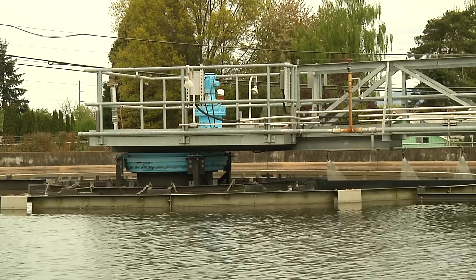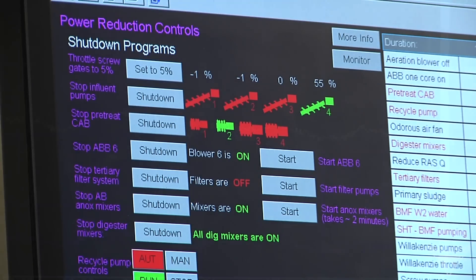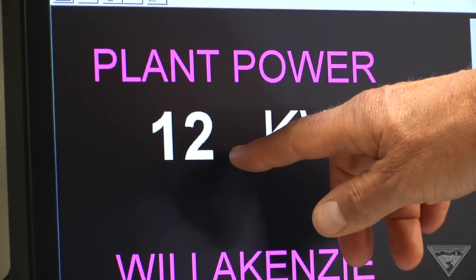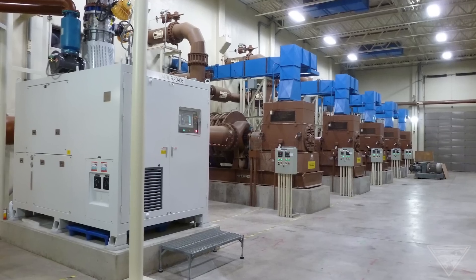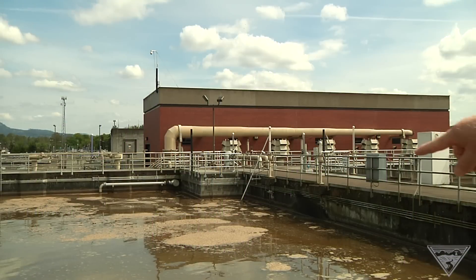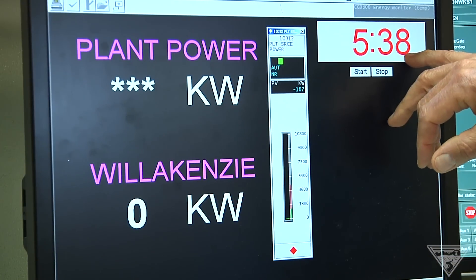As part of the pilot project, the facility was put through a series of tests to find out if it could drop its energy load, keep it at a minimum level for an hour or longer, and do so within 10 minutes. The first thing we would do is hit the blower, because that's the big ticket item. The blower has two cores, and so for long duration periods, we would turn the blower off and deactivate the second core so only one core could start — getting us through four-hour events. Once we shut off that big blower, things go fairly fast, making power shed a lot easier.